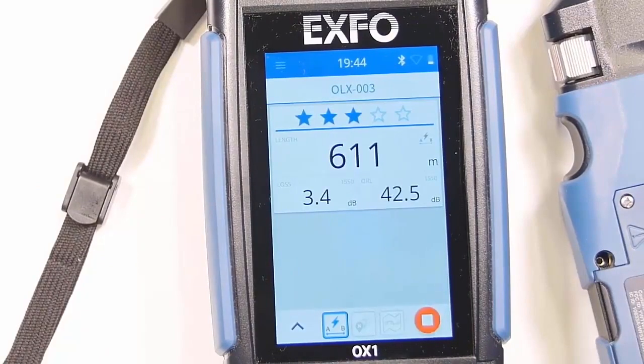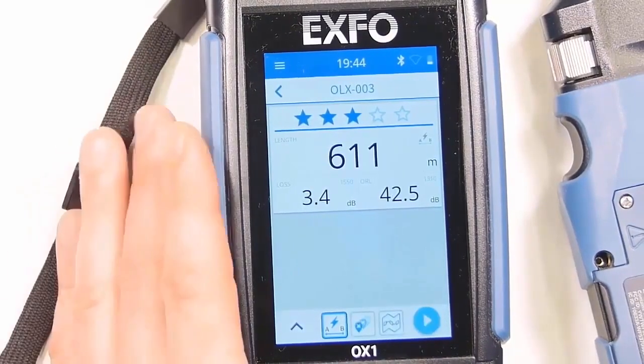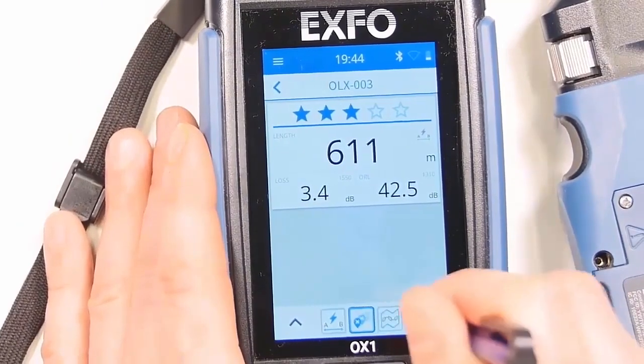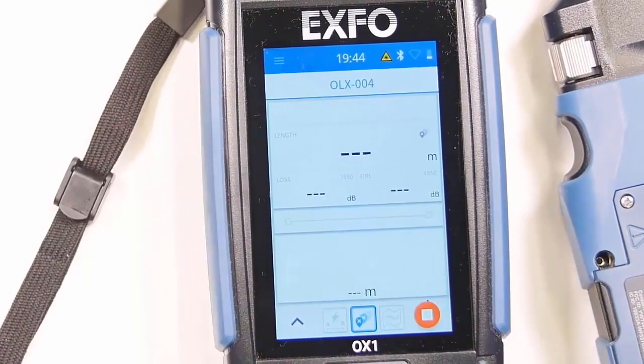Now we can see that in the event box it's seeing that it's 611 meters, showing the loss across it and ORL.